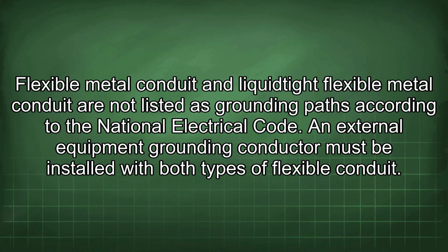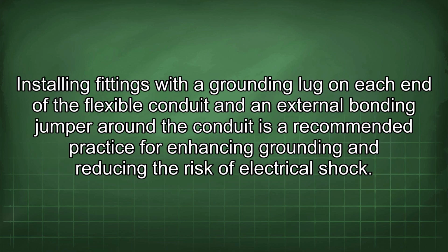Flexible metal conduit and liquid-tight flexible metal conduit are not listed as grounding paths according to the National Electrical Code. An external equipment grounding conductor must be installed with both types of flexible conduit. Installing fittings with a grounding lug on each end of the flexible conduit and an external bonding jumper around the conduit is a recommended practice for enhancing grounding and reducing the risk of electrical shock.